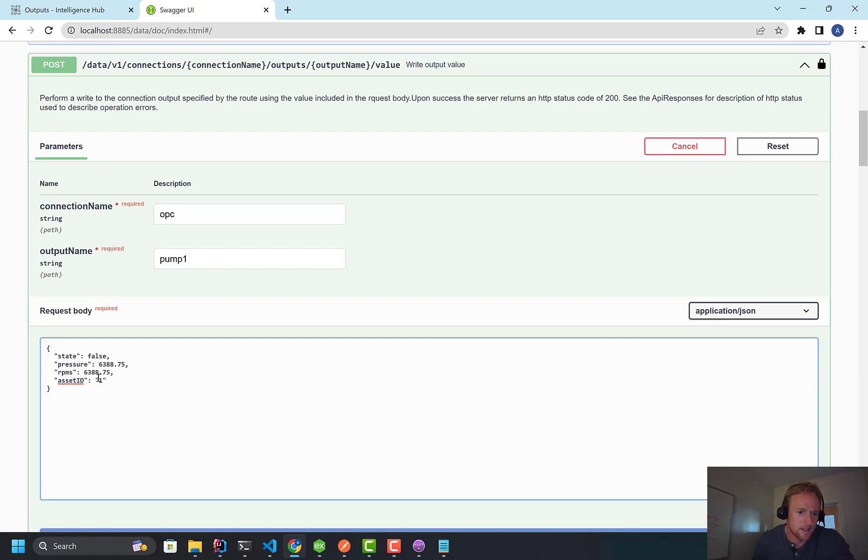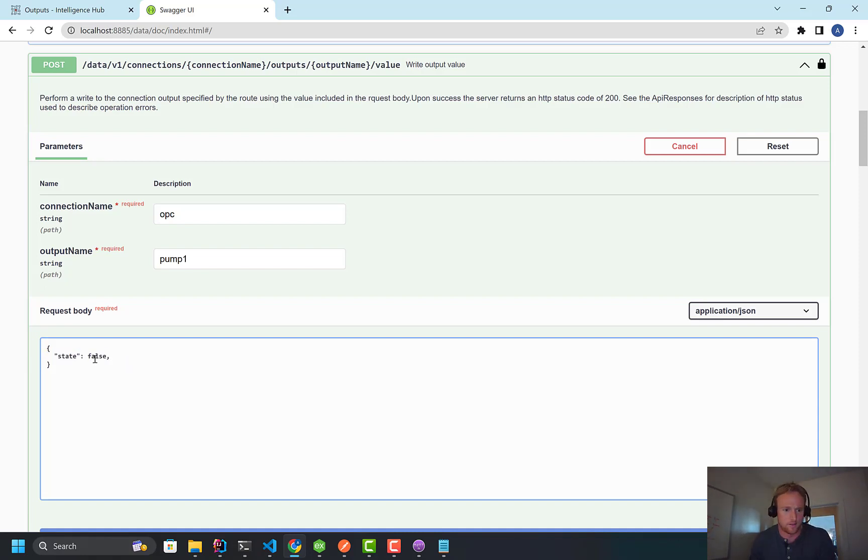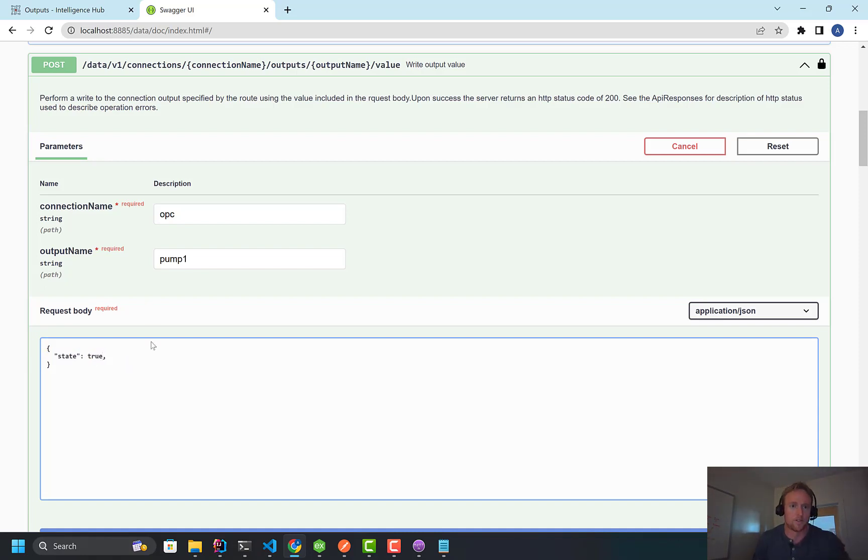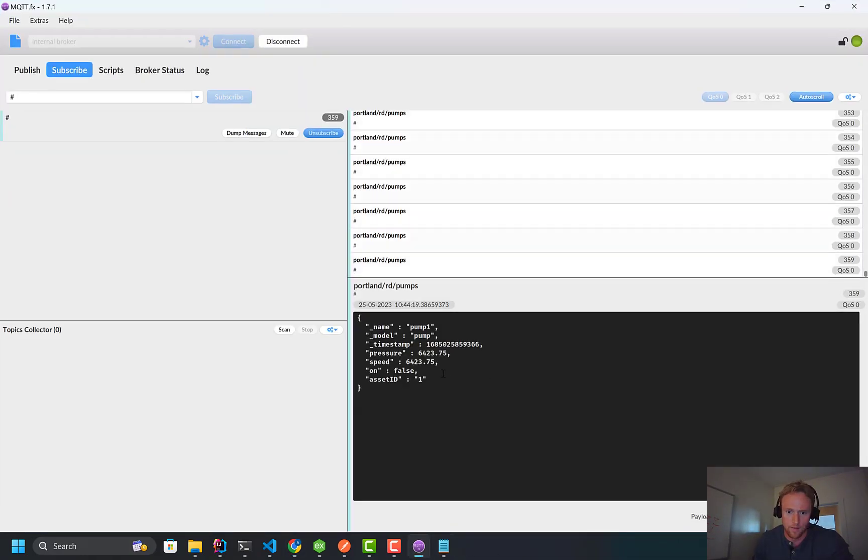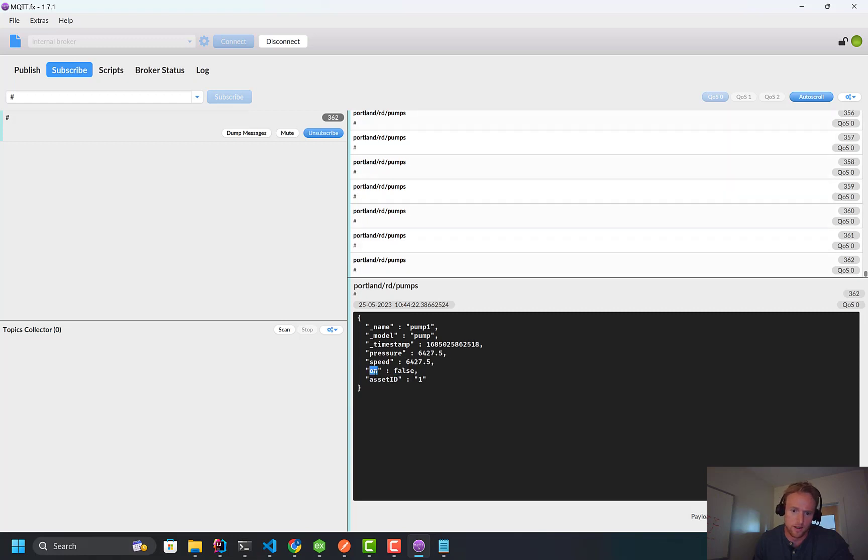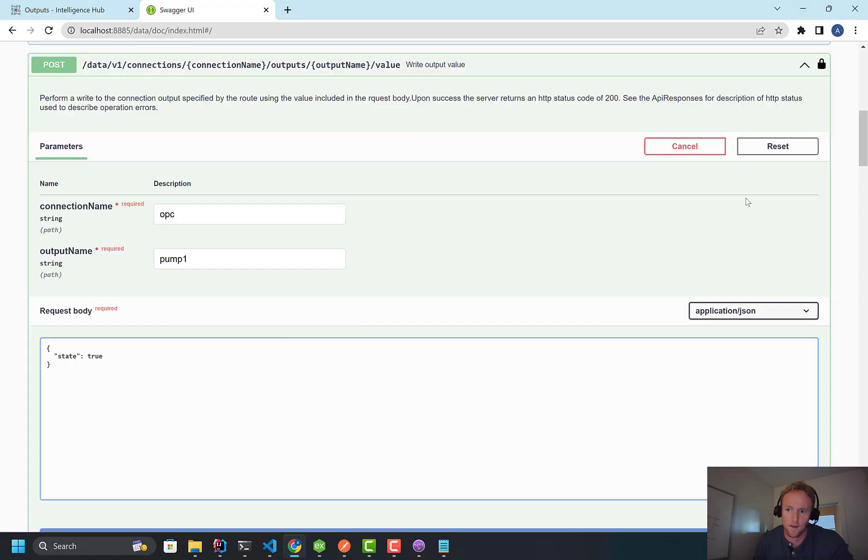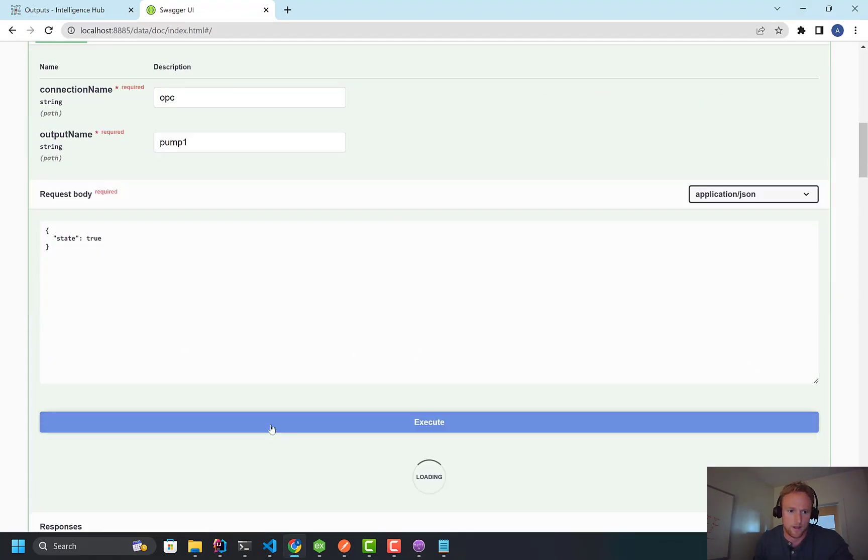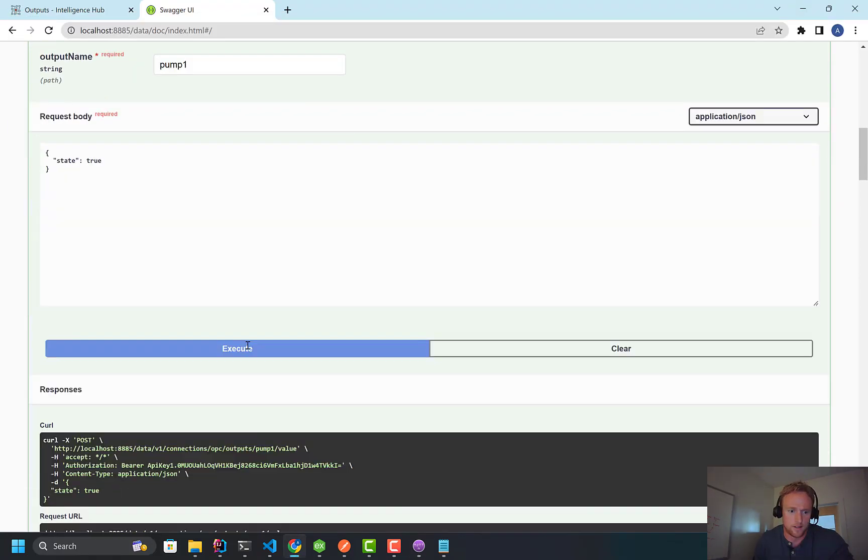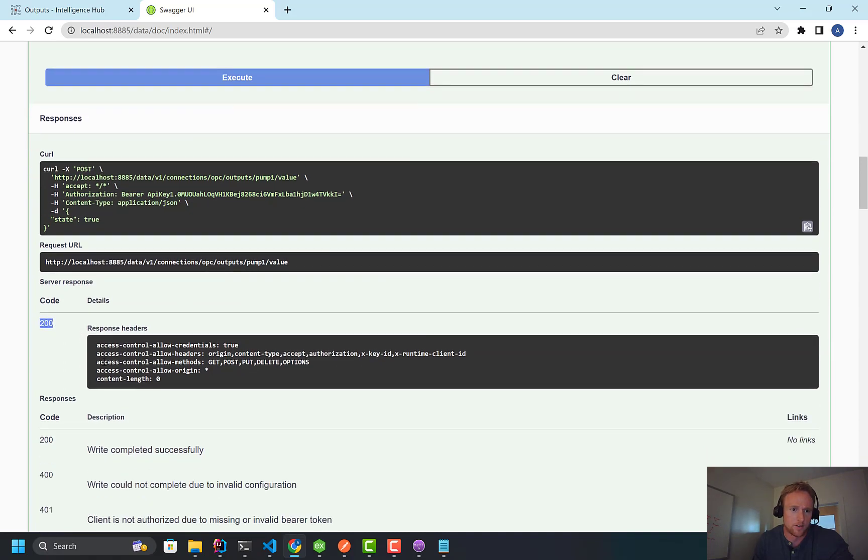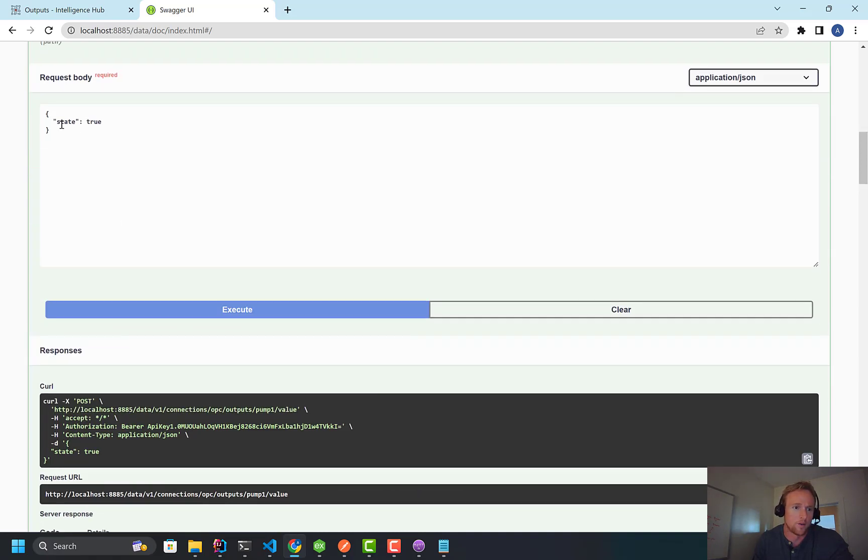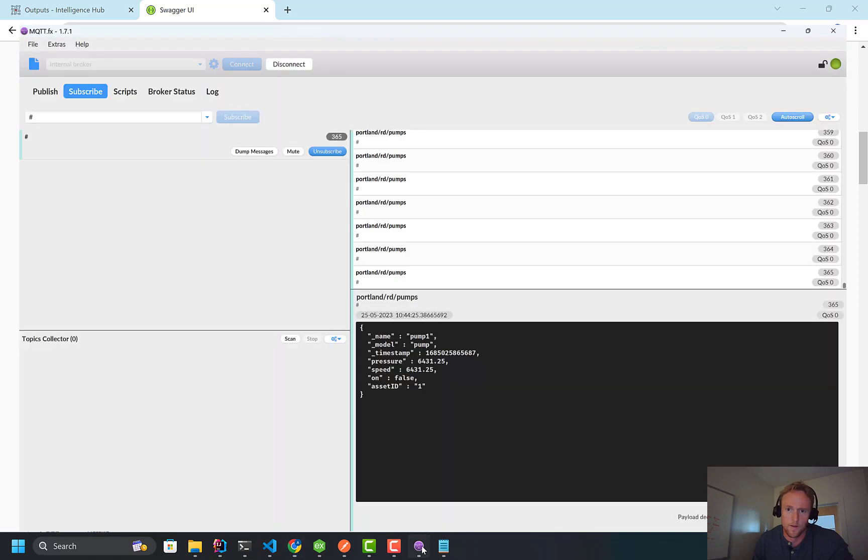Down here. And I have to issue the body. So I could write out everything. But in this case, I just want to control the state. So I'm going to turn the state from false to true. And to verify this, I'm going to go back out. The report by exception stuff, you can see the state that's driven through the instance. That state is mapped to the on attribute. And that's false. I'm going to set it to true. So I'm going to execute this. And this is going to come back and say success 200. So it went through. It found this tag in the OPC server and flipped it to true. And then if we go back to the report by exception, you can see we switched that bit.